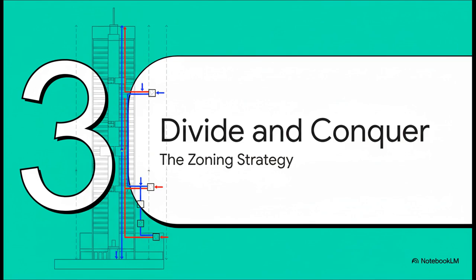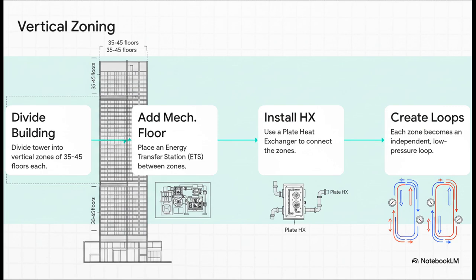We're going to divide and conquer by breaking the building into vertical zones. Here's the game plan. We slice the skyscraper into these manageable chunks, say 40 floors each. Then, between each of these zones, we stick a dedicated mechanical floor. And on that floor, we build an energy transfer station. What this does is it creates these completely separate low-pressure water loops that only have to serve their own little section of the building.